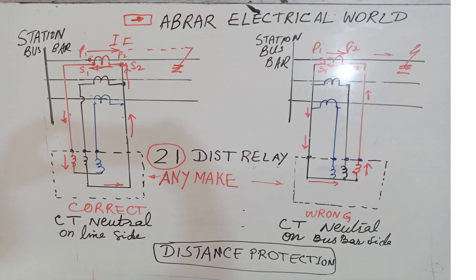Here is the diagram I have drawn on the whiteboard. On the left-hand side it says 'Correct' — CT neutral on line side. On the right-hand side it says CT neutral on busbar side, which is wrong. It is wrong because we are preparing a scheme for distance protection of a transmission line. You can see the transmission line and the fault location. First look at the correct diagram. The dotted points show the polarity of the CT.